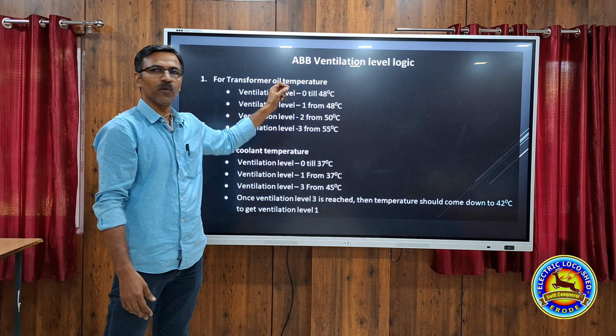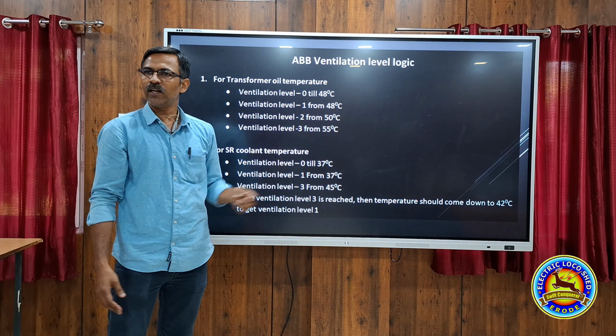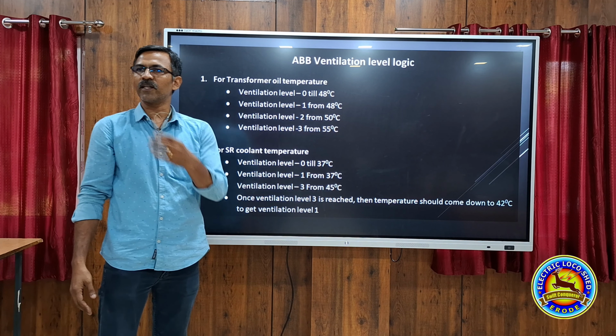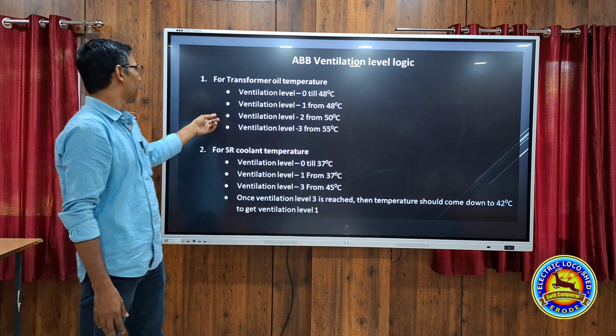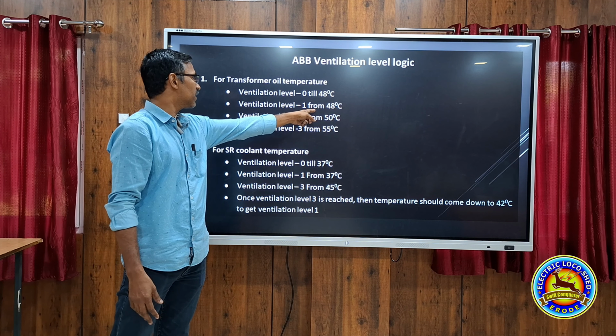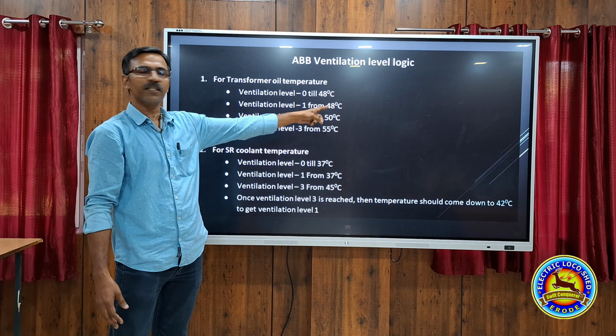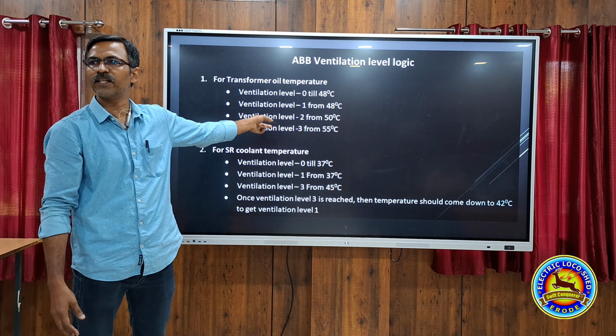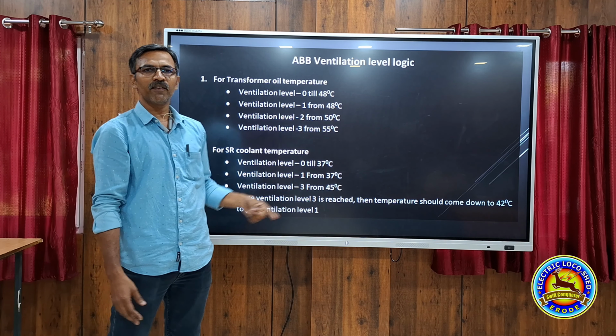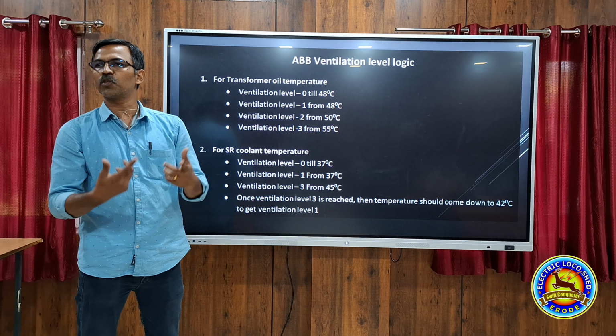Ventilation level 0: if the transformer oil temperature is less than 48 degrees, the OCB will not work. Bar 1 will not work. There is no ventilation required at that time. Ventilation means the running of the OCB, flowing of air through the radiator. When the temperature reaches above 48, it will start ventilation level 1. Ventilation level 1 means the OCB will start at low speed.